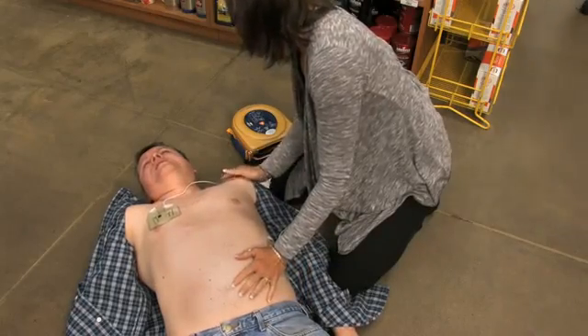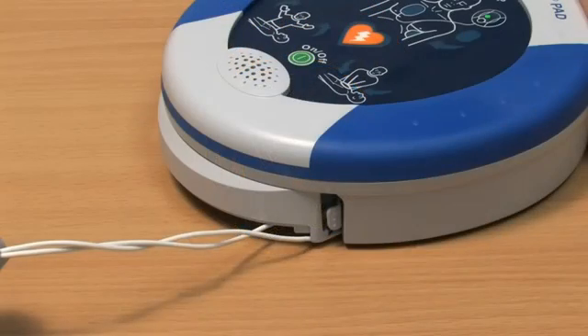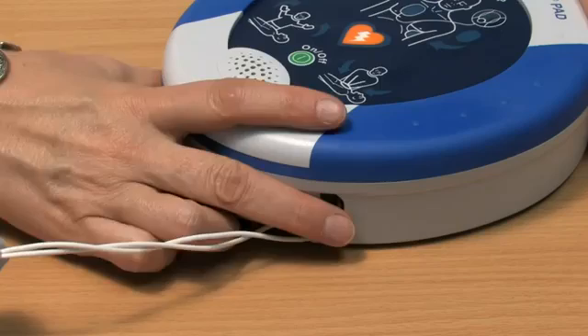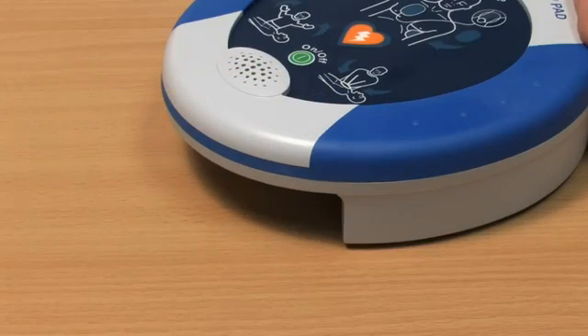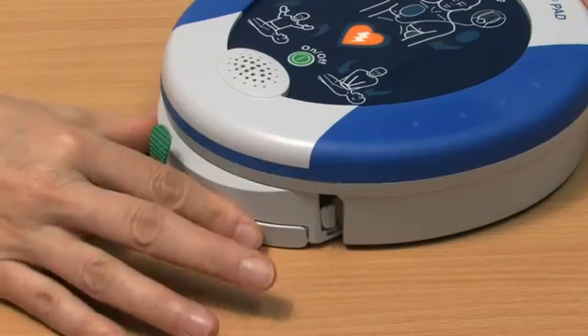One note for rescuers: the Samaritan PAD can be used while in its protective case or out of it. After using the Samaritan PAD, contact your HeartSine channel partner to purchase a replacement pad pack. Slide a new pad pack into the unit and store it as usual.